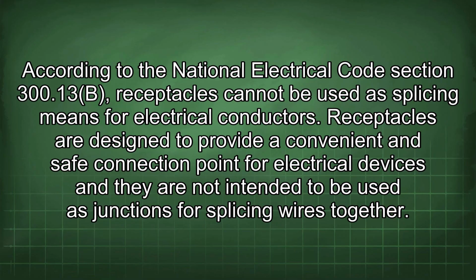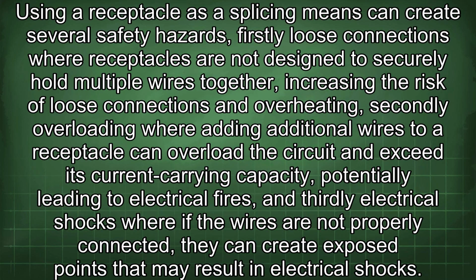According to the National Electrical Code Section 300.13(B), receptacles cannot be used as splicing means for electrical conductors. Receptacles are designed to provide a convenient and safe connection point for electrical devices, and they are not intended to be used as junctions for splicing wires together. Using a receptacle as a splicing means can create several safety hazards.